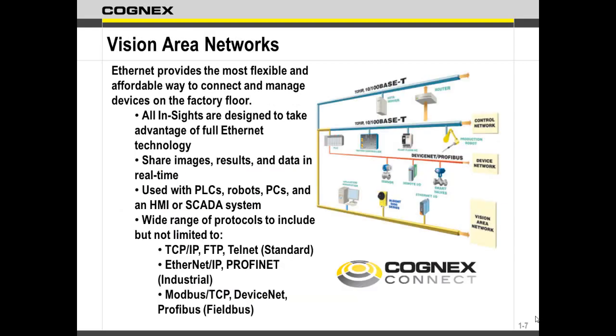Now, all the units are Ethernet, okay? So when you connect up to it, at a minimum, you're probably going to at least be setting what your IP address is and giving it a job. Even if it's just, hey, I'm replacing it or something, you're still going to have to, at some point, get Ethernet connectivity to it to put this stuff on. Now, it doesn't have to run with it. As soon as you have it all set up, you've got the job running, it doesn't have to be on Ethernet unless you're using Ethernet to control it. Otherwise, you could pull it off and off it runs. It can tell its I/O module, kick it off, save it, whatever they want to do.